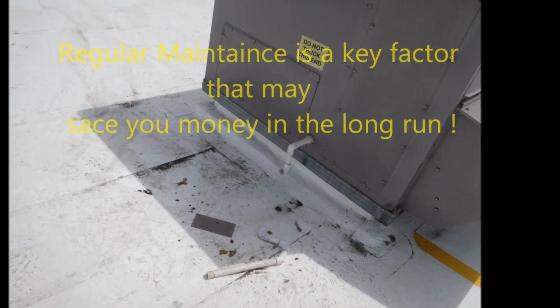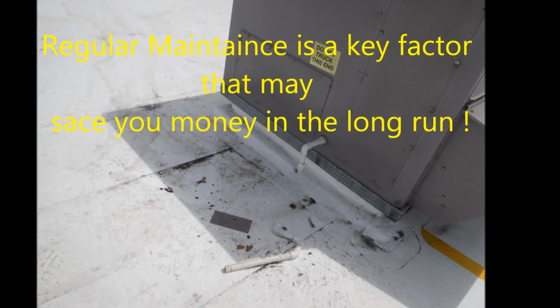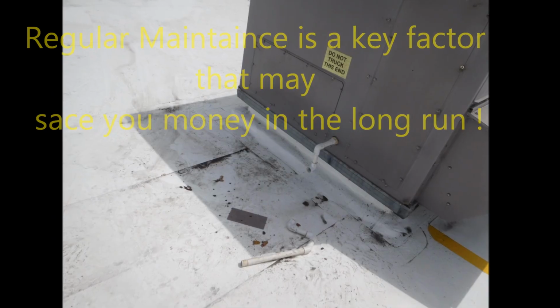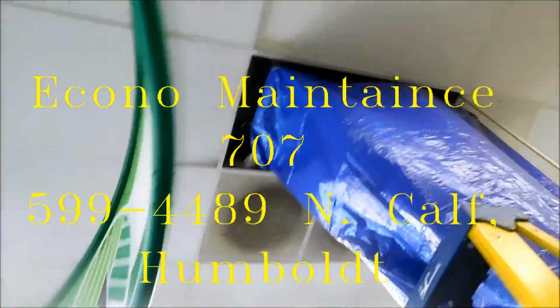There's our leak area. So the condensate drain on that HVAC unit was plugged up. And it caused all this problem. So that should be a lesson in maintenance for you. If you don't maintain the condensate drains, then you get leaks. And you have to call me to come and fix everything.